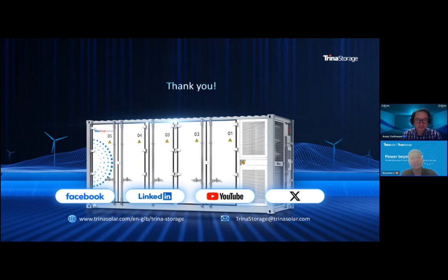Based on all these testing facilities, we can better validate, as I mentioned at the very beginning, the performance of the DC container, as well as the PCS, and the compatibility and communication between all this equipment. So customers can simply make a plug and play before the full operations of the systems. Okay, thank you.